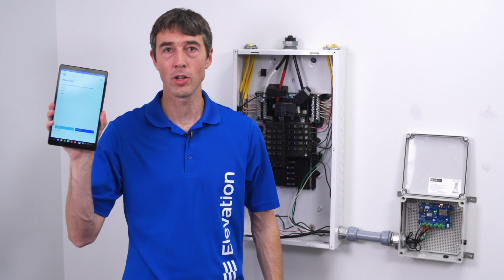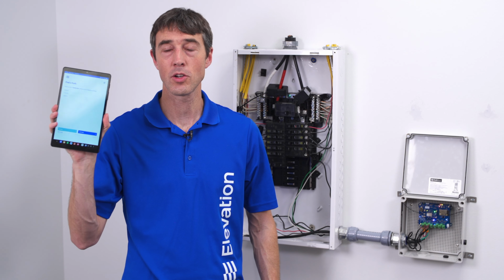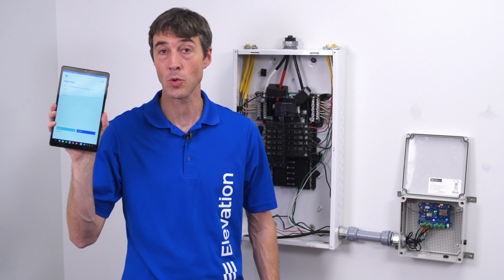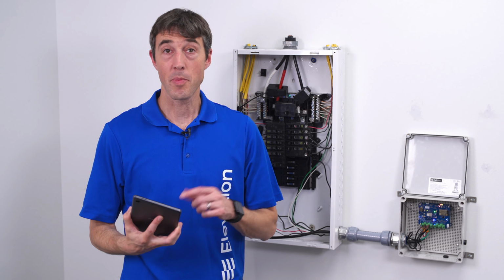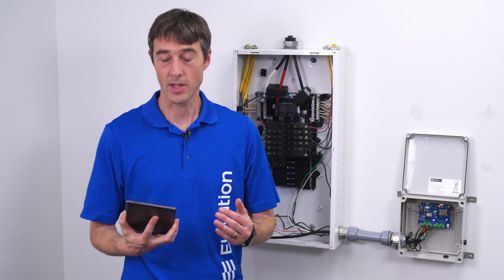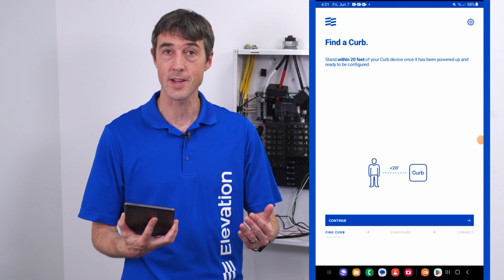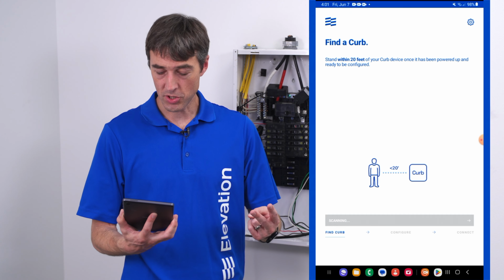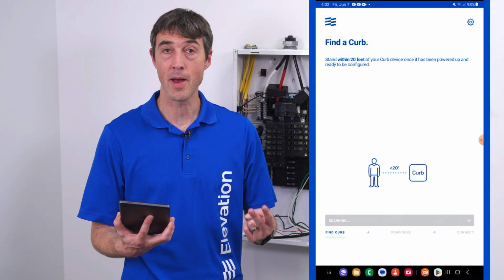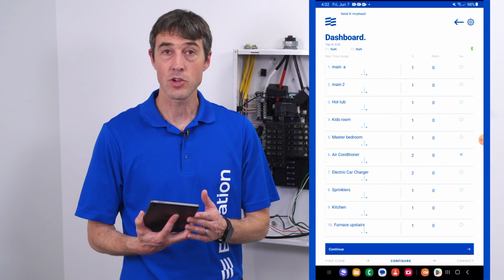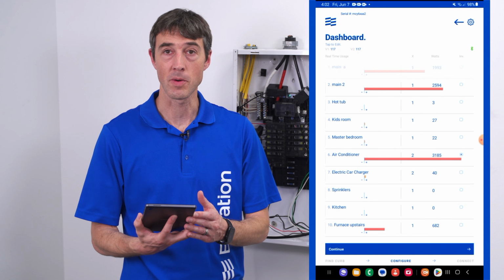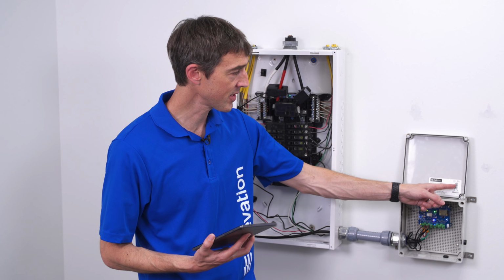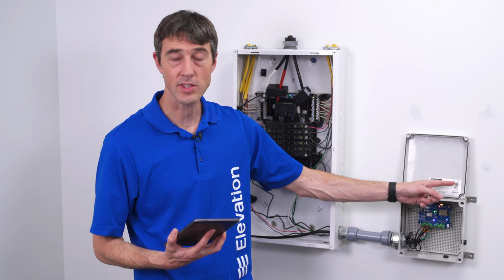Step 4 of installing the Curb M10 unit is configuring the device. Configure the device using the Curb Installer app, which is a different app than the existing Curb app on the different Play stores and Apple stores. The first step of configuring that Curb device involves signing in with your installer credentials. Step 2 would be scanning for the Curb M10 that is local to you, and you're able to identify it by the individual serial number. The serial number for the Curb device is listed inside the cover on the individual device, and you can match it up with the serial number that's presented in the installer app.